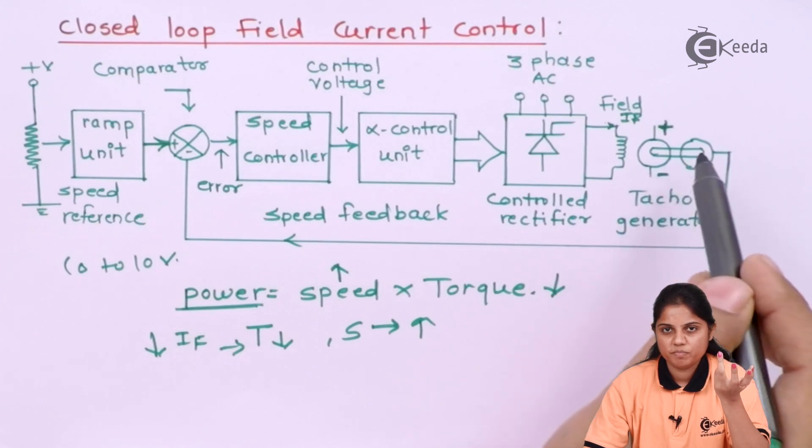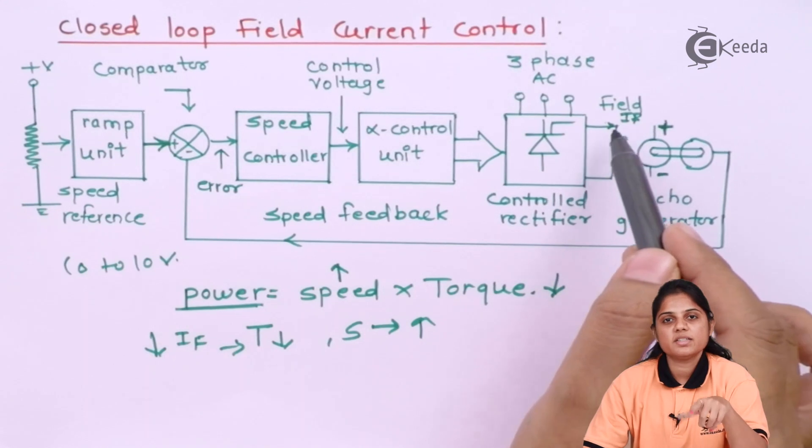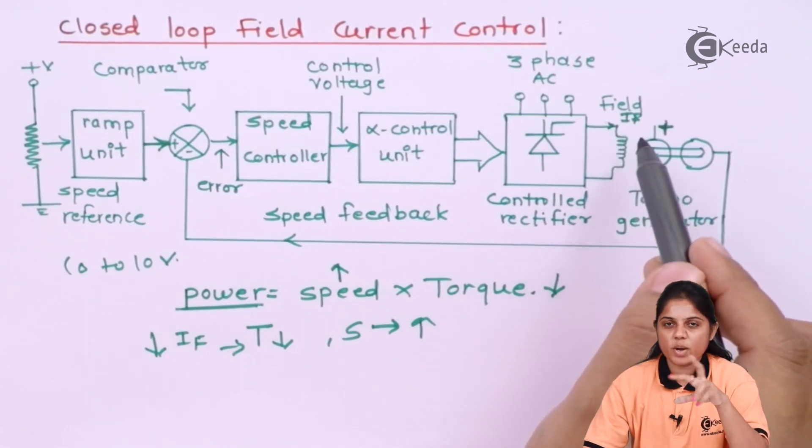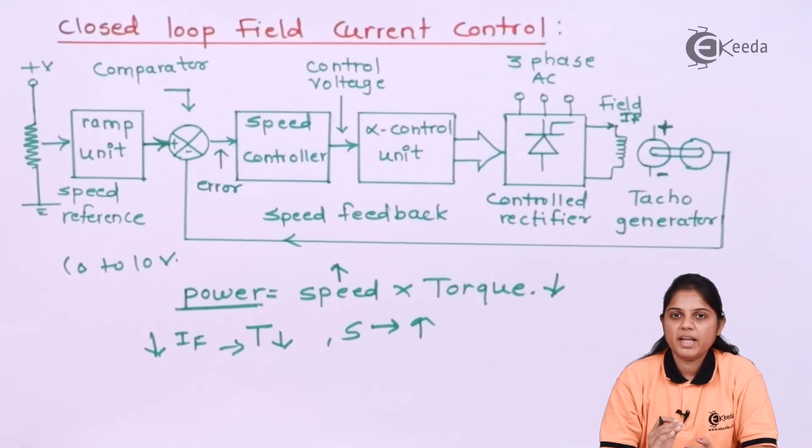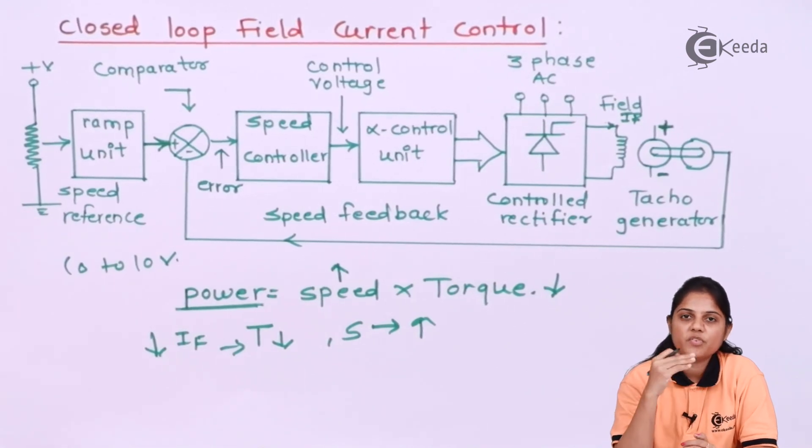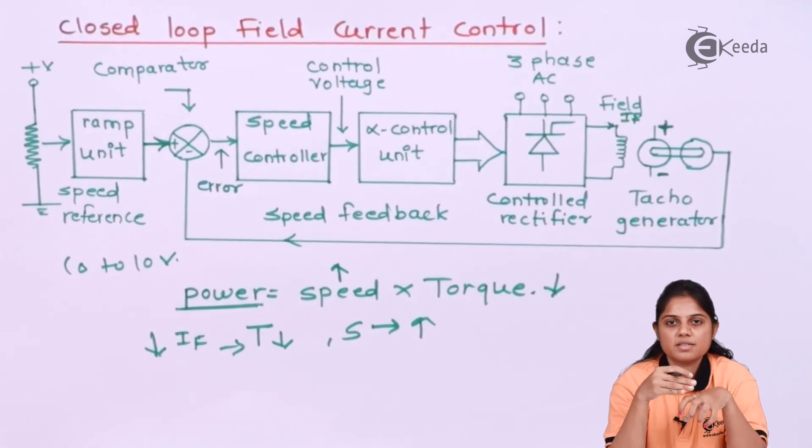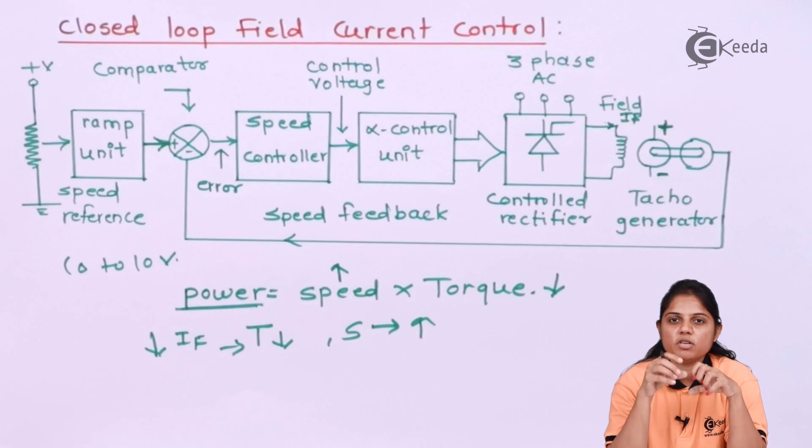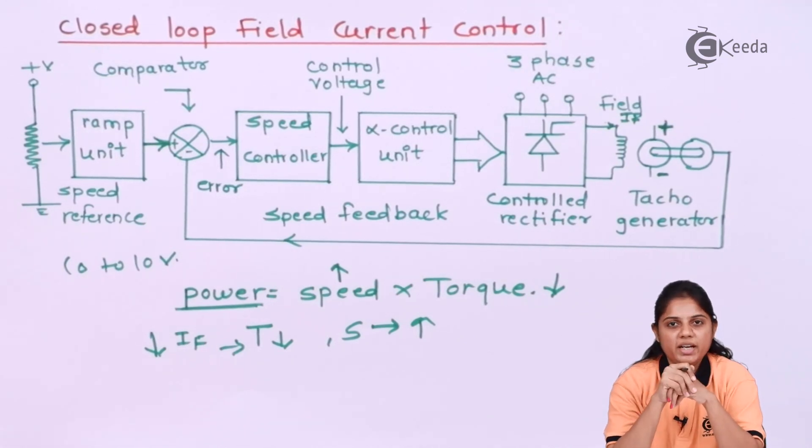If the speed is more than required, then you need to increase the field current. You have to remember this vice versa operation. If your speed is more than required, then you need to increase field current because if you increase field current your speed will decrease. But if you are working at a speed which is less than the required amount, then you have to decrease the field current. If you are decreasing the field current, your speed will automatically increase and you can reach the required level.